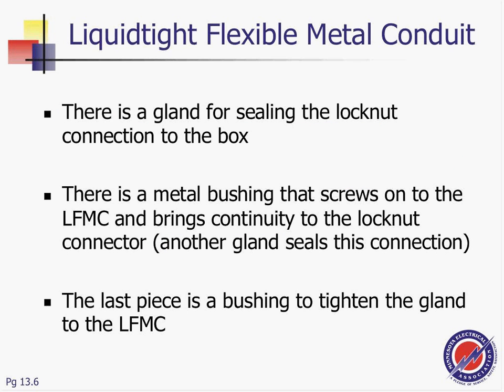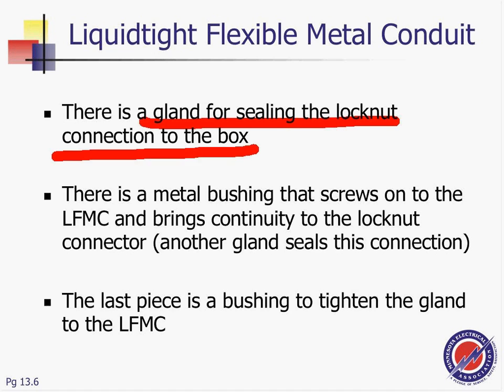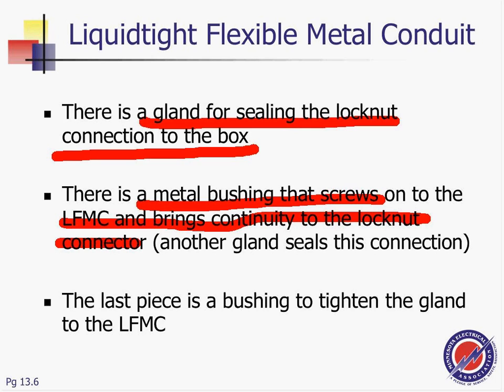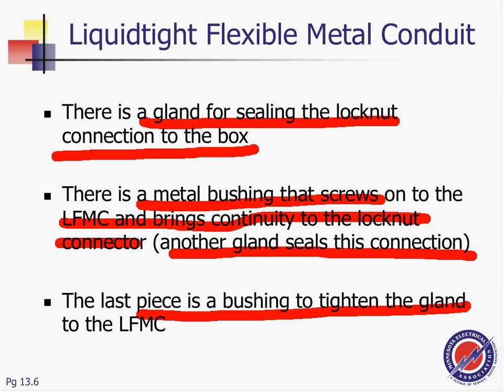Okay. There's a gland for sealing the lock nuts and connector to the box. So everything is sealed here. There's a metal bushing that secures onto the Liquidtight flexible conduit and brings the continuity to the lock nut connector. So the connector comes with a special type of connector, and the idea obviously is to maintain the seal, the Liquidtight. So it's a jacketed flexible metallic conduit. The connector has lock nuts and seals that seal it completely against water. The last piece is bushings to tighten the gland, and this is just the connector, guys, that goes with it.